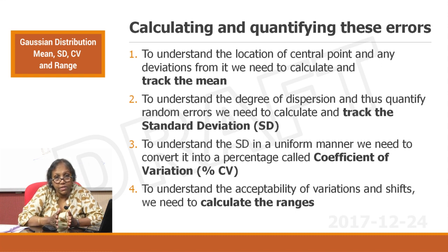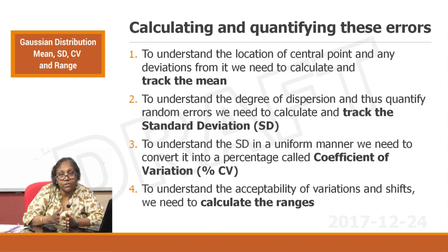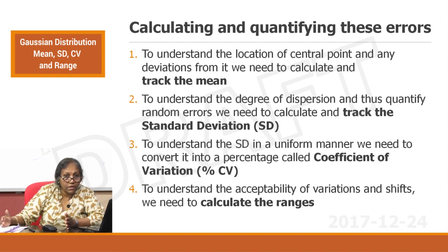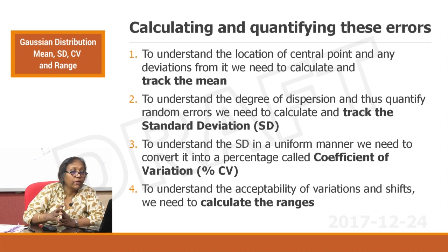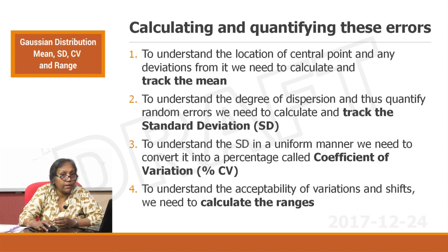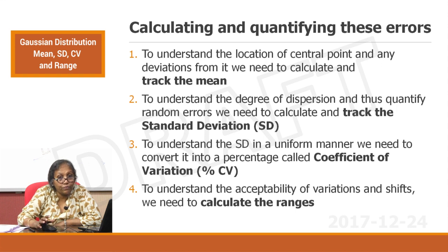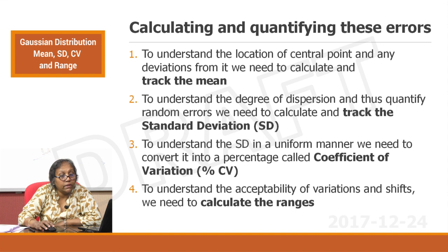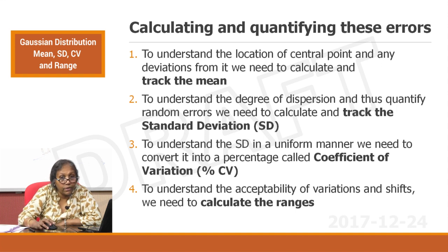What was the standard deviation today, what is it next week, what is it at the end of the month — the standard deviation has to be tracked. The third parameter that will help you in monitoring the system is the CV or coefficient of variation, which is nothing but converting the standard deviation into a percentage of the mean.